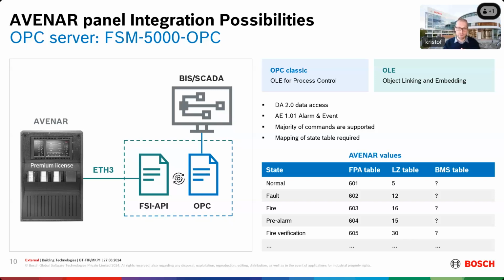So you need to get in contact with the supplier of that system and ask them, which number is representing a fire in your building management system? Maybe it is a number like 423, then you need to fill out 423 here, and then the conversion is made. In case of a 603, it's a 423 in the BMS, so the fire is displayed correctly. And this is something we cannot do for you, because it is specific to the SCADA system, the building management system. So this definitely needs to be done by the supplier of that system.